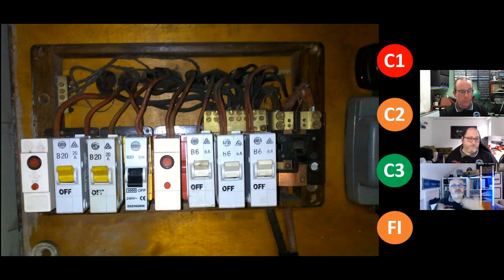And depending on your extent of limitations, you may actually turn around and say, well, this could potentially be a C1, because you can see some idiots twisted all the CPCs together. What happens if you untwist them and they all break? You don't have any earth continuity. It may be that the installation is life expired. Well, that's a good point, because obviously that twisted protective conductors there compromises your ability to inspect it.